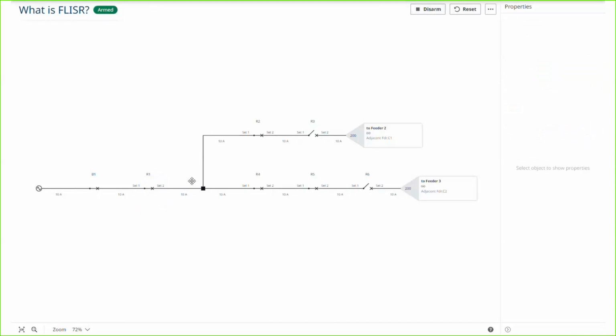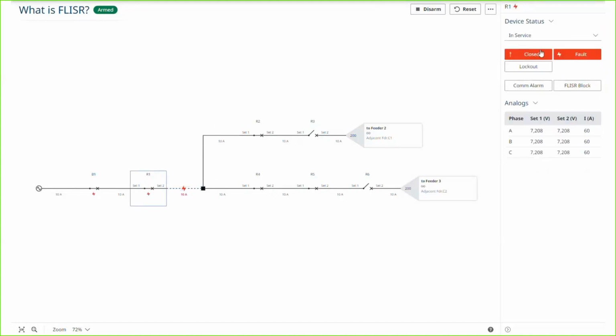So now we're going to arm FLISR. We're going to do the exact same thing again. There's a fault on the line. The recloser trips, and FLISR does nothing. There's no lockout. Most faults are temporary. So let FLISR sleep until the recloser locks out.